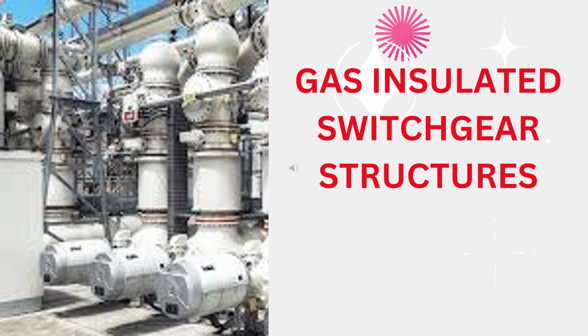GIS shall be of the freestanding, self-supporting type with easy accessibility to all the parts during installation and maintenance, with all high voltage equipment installed inside gas insulated metallic and earthed enclosures, suitably subdivided into individual arc and gas-proof compartments, preferably for busbar disconnectors, intermediate compartments, circuit breakers, line disconnectors, current transformers, voltage transformers, gas insulated bus duct section between GIS and XLPE cable, gas insulated bus section between GIS and transformer reactor.